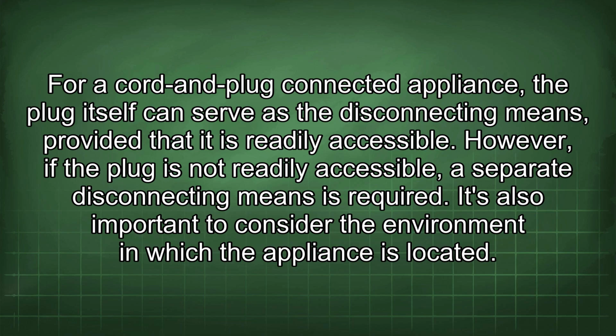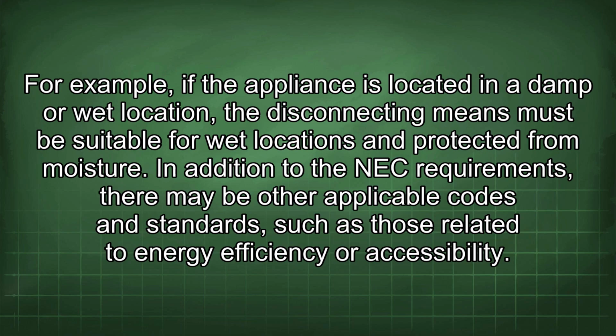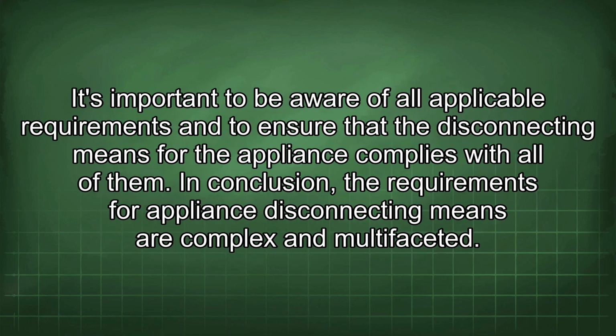It's also important to consider the environment in which the appliance is located. For example, if the appliance is located in a damp or wet location, the disconnecting means must be suitable for wet locations and protected from moisture. In addition to the NEC requirements, there may be other applicable codes and standards, such as those related to energy efficiency or accessibility. It's important to be aware of all applicable requirements and to ensure that the disconnecting means for the appliance complies with all of them.